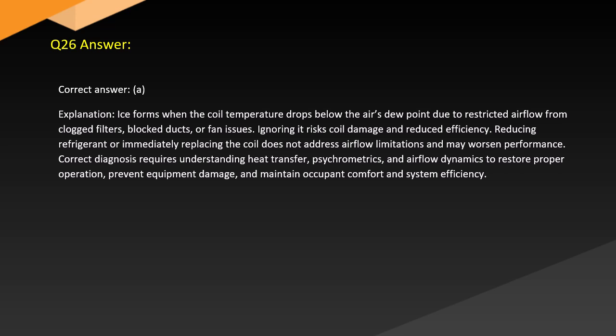Answer. Correct answer. A. Explanation. Ice forms when the coil temperature drops below the air's dew point due to restricted airflow from clogged filters, blocked ducts, or fan issues. Ignoring it risks coil damage and reduced efficiency. Reducing refrigerant or immediately replacing the coil does not address airflow limitations and may worsen performance. Correct diagnosis requires understanding heat transfer, psychrometrics, and airflow dynamics to restore proper operation, prevent equipment damage, and maintain occupant comfort and system efficiency.